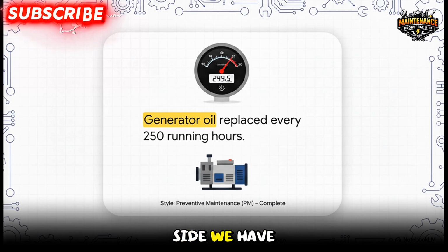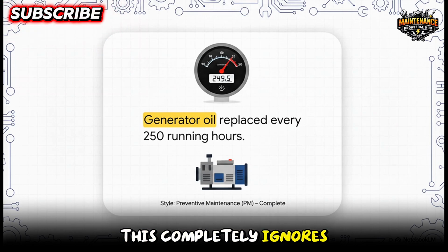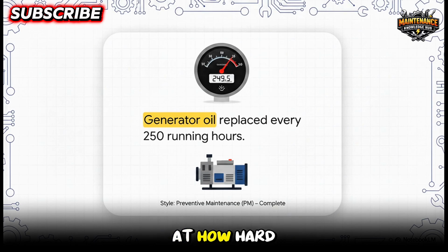On the flip side, we have usage-based maintenance, or UBM. This completely ignores the calendar and looks purely at how hard the machine is actually working. A perfect example? Replacing the oil in a diesel generator every 250 running hours. If the generator just sits idle for a year, you don't change the oil because 12 months went by.